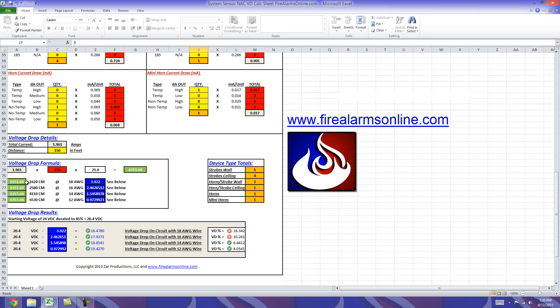And each of these represent the four different options you have for wire gauge as we have to divide those by the circular mils. So for an 18 gauge wire our circular mils are 1620, 16 gauge 2580, 14 gauge 4110, 12 gauge is 6530.